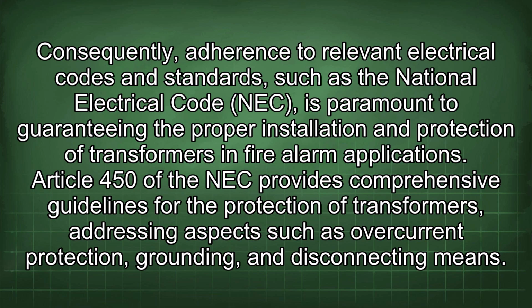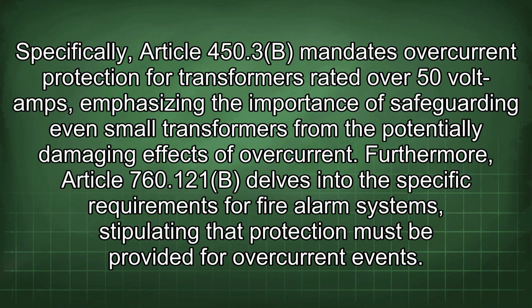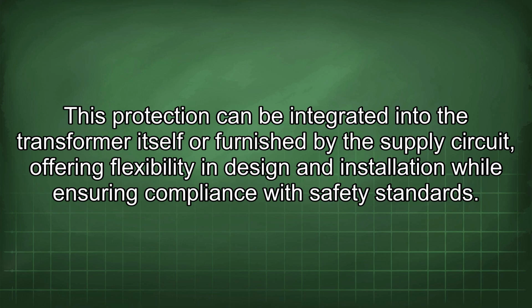Article 450 of the NEC provides comprehensive guidelines for the protection of transformers, addressing aspects such as overcurrent protection, grounding, and disconnecting means. Specifically, Article 450.3b mandates overcurrent protection for transformers rated over 50 volt amps, emphasizing the importance of safeguarding even small transformers from the potentially damaging effects of overcurrent. Furthermore, Article 760.121b delves into the specific requirements for fire alarm systems, stipulating that protection must be provided for overcurrent events. This protection can be integrated into the transformer itself or furnished by the supply circuit, offering flexibility in design and installation while ensuring compliance with safety standards.